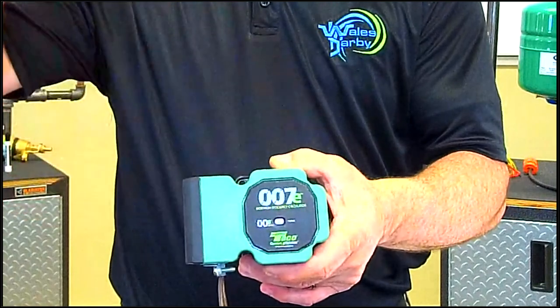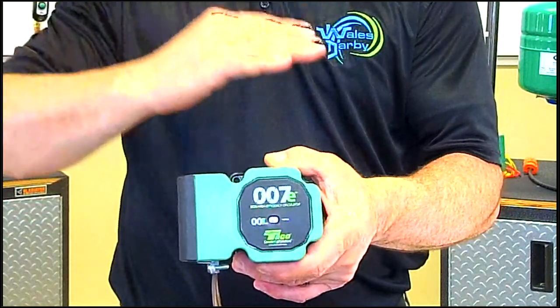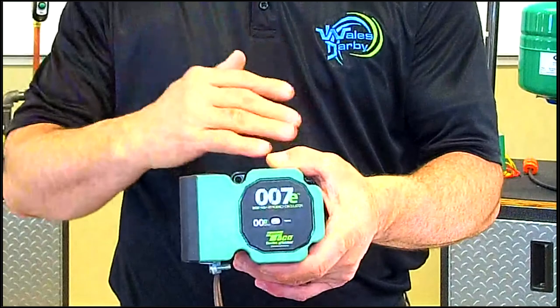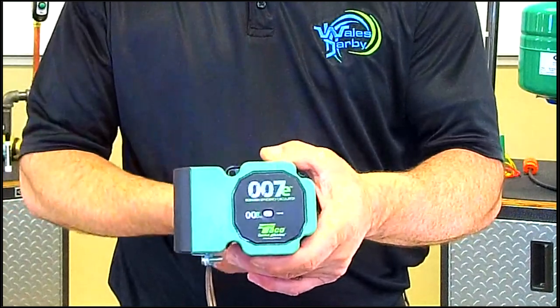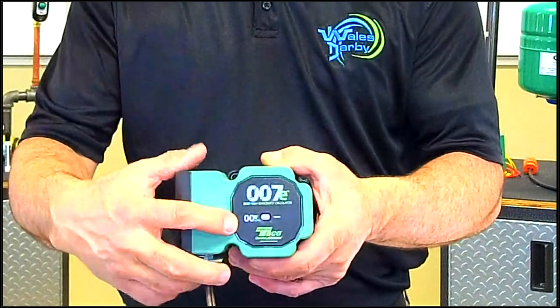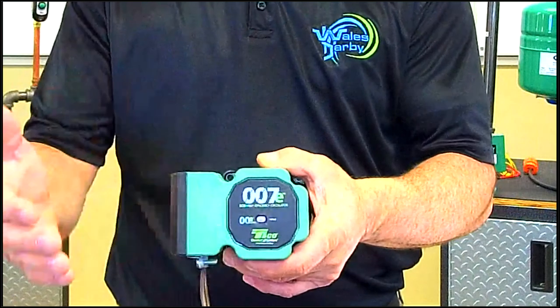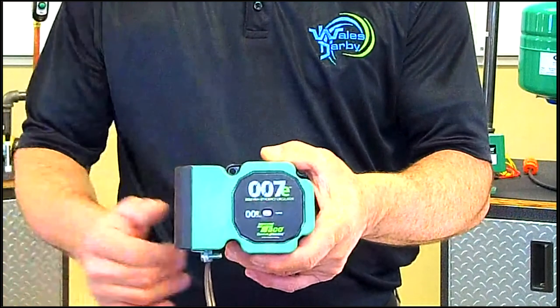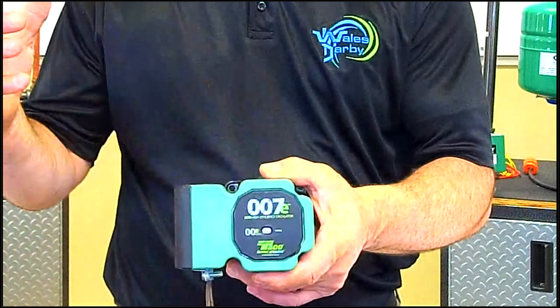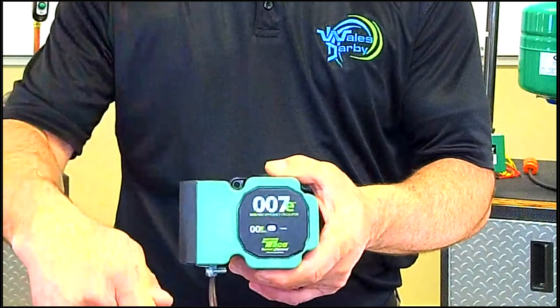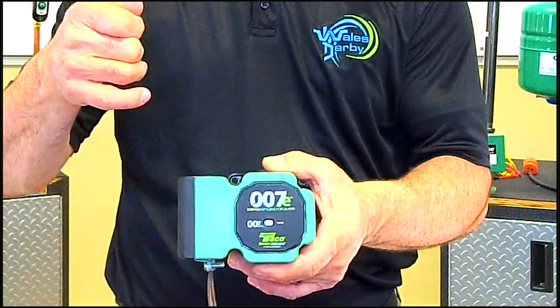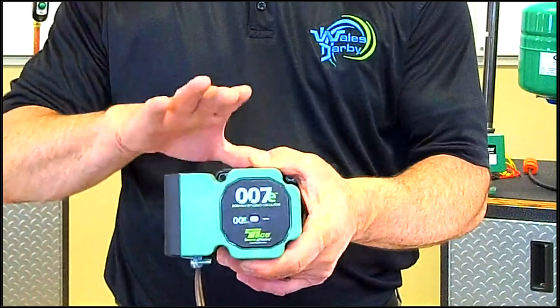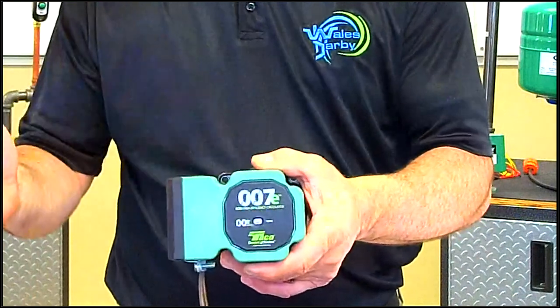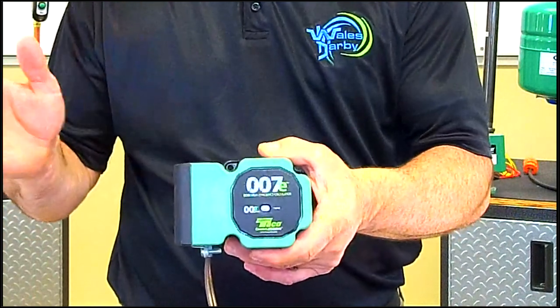It will ramp the RPM up to 6,000 RPM and back down up to 100 times. And if it can't move the air pocket, it will turn red and let you know that the circulator has shut off for a reason. You can go there, purge out the heat circuit, power the circulator down, and power it back up. The circulator is good. It will run again, where an AC circulator will sit there and burn itself out.